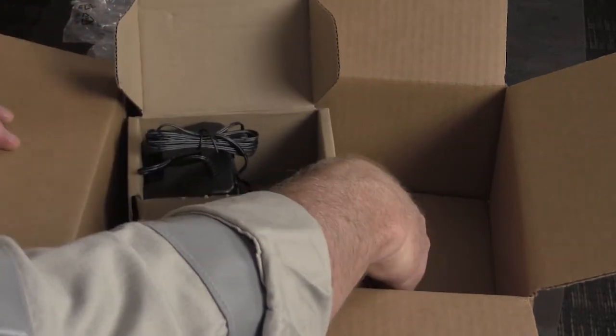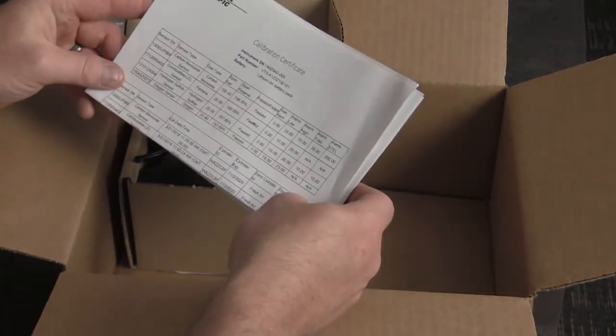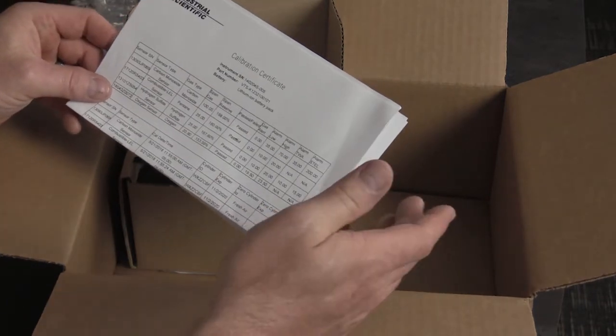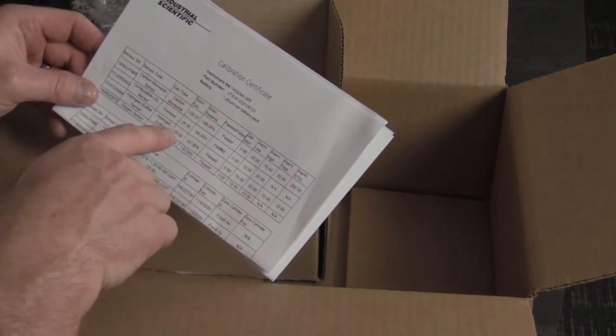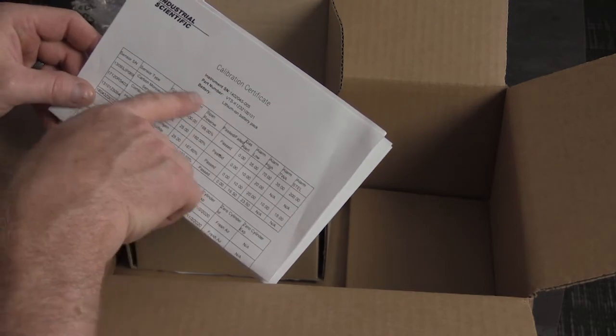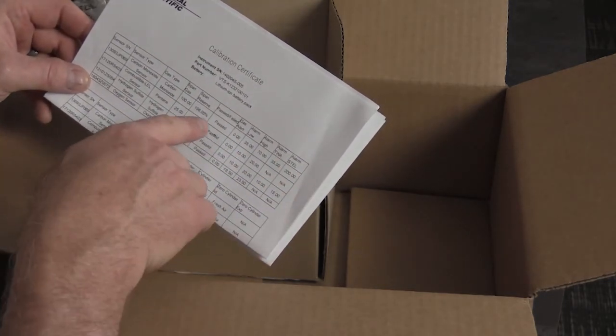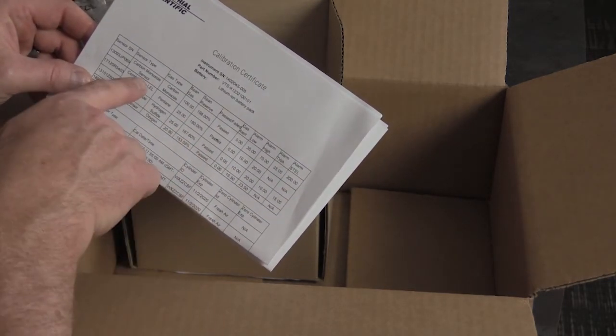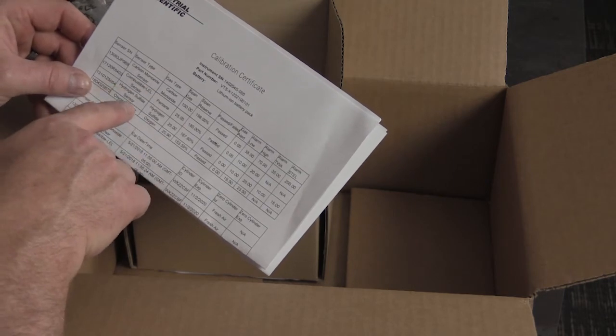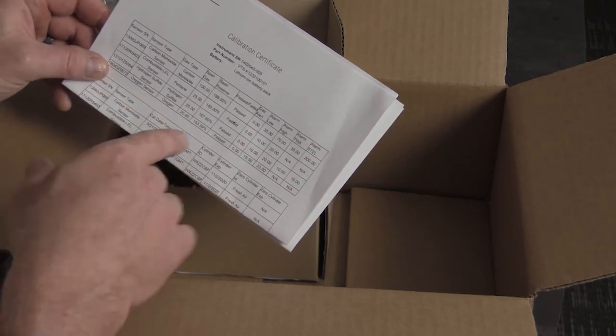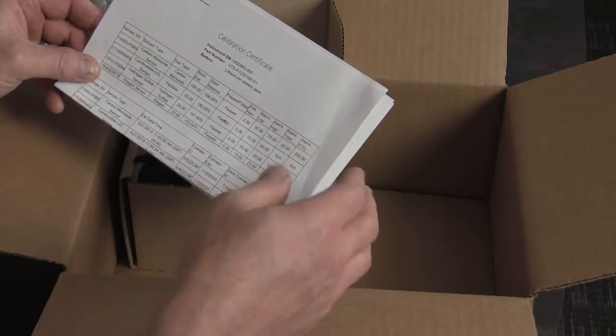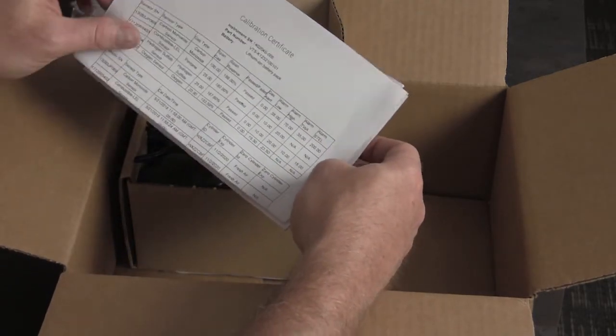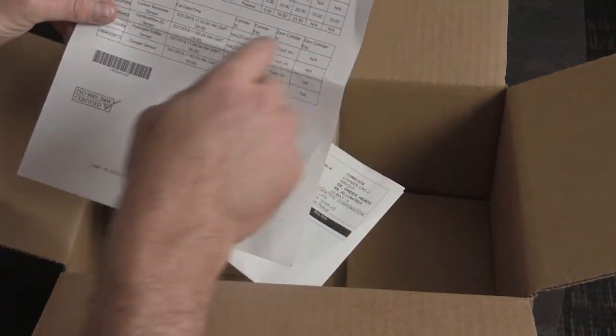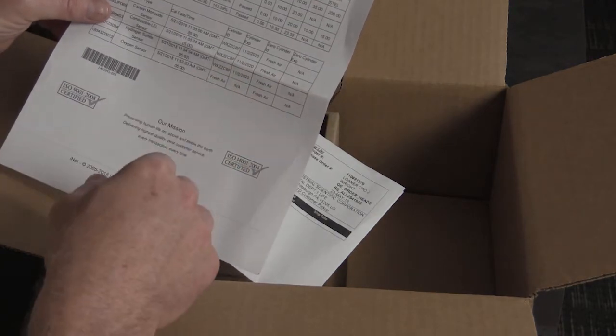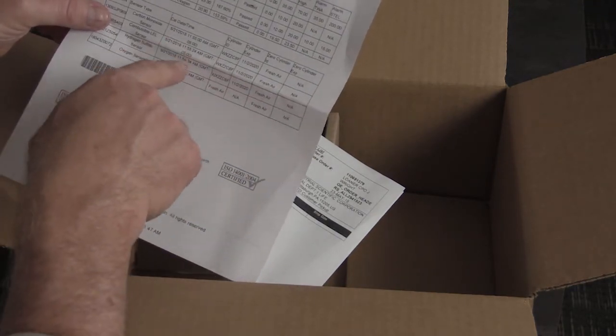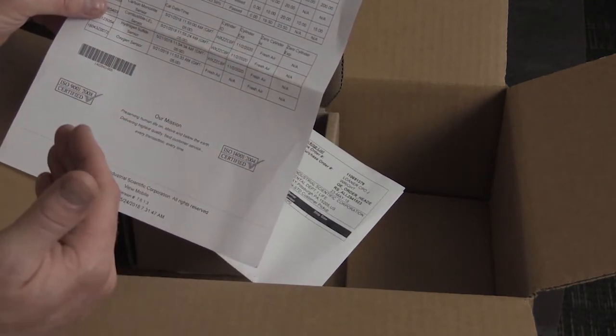And then we've got a couple of pieces of paper in the bottom of the box here. This is a calibration certificate specifically for this instrument. Has all of the calibration data that I would need. They all pass the calibration - CO sensor, LEL, H2S, oxygen sensor - all of the alarm set points from the factory. And then there's even additional information about the cylinder that was used to calibrate it: expiration date, cal date and time, all of that's included.